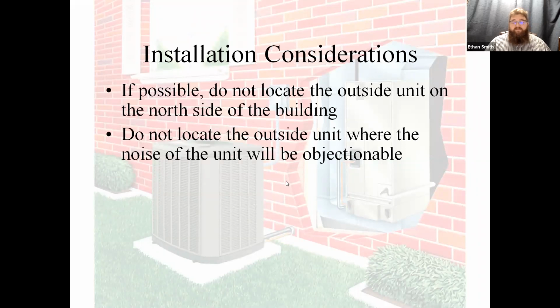Okay. The other big thing we see with heat pumps, guys, is don't put them outside bedroom windows. Don't put them anywhere where the noise of the unit is going to be objectionable. The colder it gets outside, the louder your heat pump's going to sound. When these things go into defrost, they generally make a lot of noise. So we definitely don't want to be putting them outside the master bedroom window next to their bed. I actually have an installation that I visit almost yearly for a contractor where they've installed these things right outside the master bedroom, and the homeowner has to be reconvinced every year that there's nothing wrong with the unit because it made this whoosh banging noise in the middle of the night and woke him up.